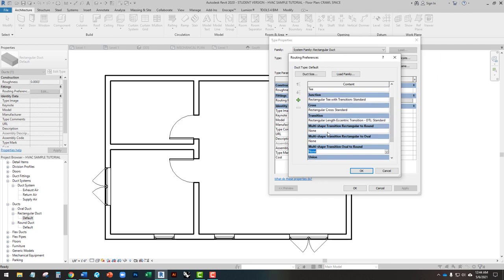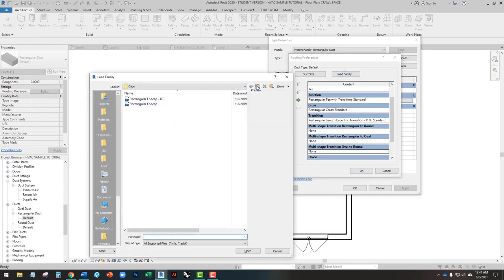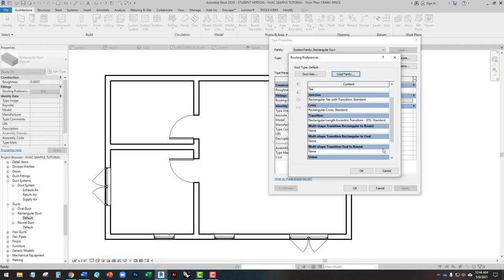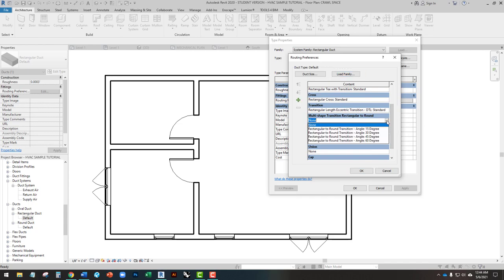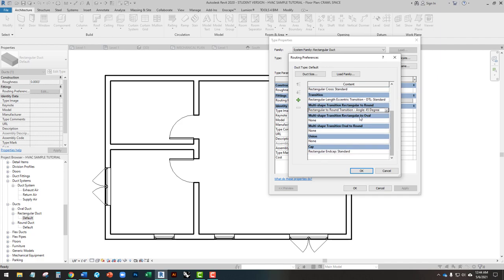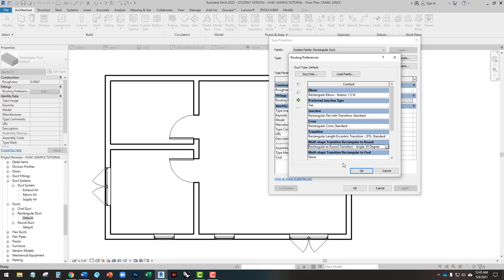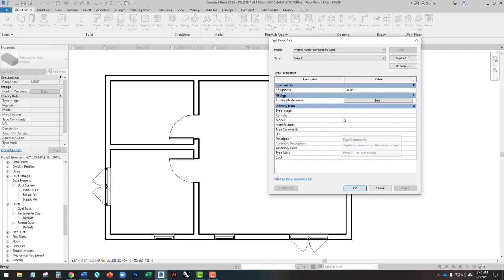Let's also load the Multi-Shape Transition Rectangular to Round. To find that we'll go to Multi-Shape Transition, then Rectangular to Round — we can do it by length or angle, and we'll use 45 degrees. We're not going to use oval, so we don't have to worry about that. Now we have transitions and multi-shape transitions — this will inform Revit how to go from a rectangular duct to a round duct. We'll hit OK.